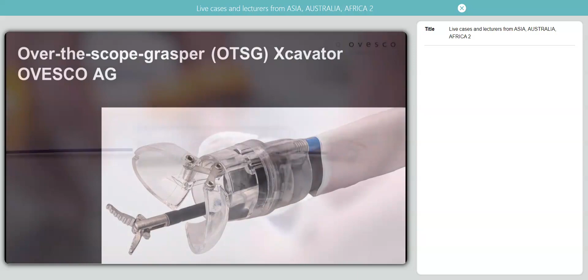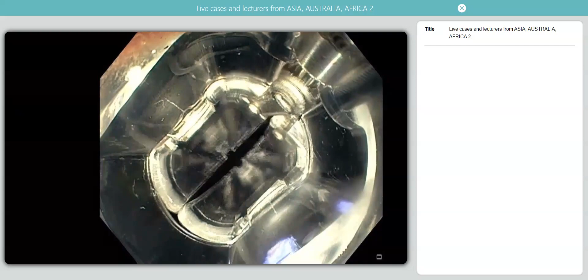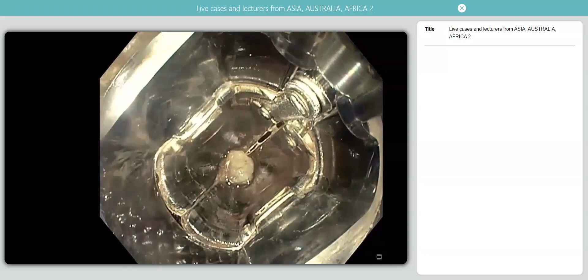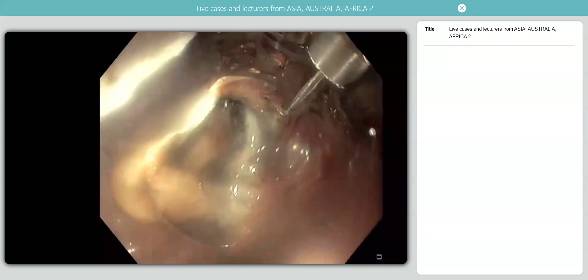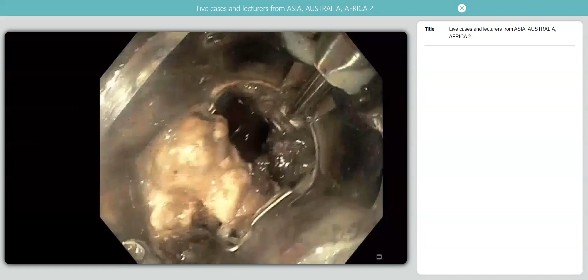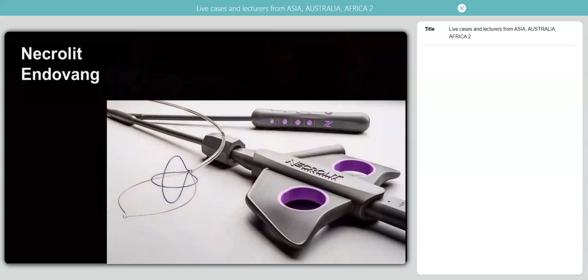The second device for endoscopic necrosectomy is the over-the-scope grasper Xcavator by Ovesco. It is a grasper mounted over the scope with a scoop span of about 28 mm. It is suitable for gastroscopes with an outer diameter between 9.5 and 10.5 mm. Once mounted, it adds about 4 to 5 mm to the outer endoscope diameter, and its passage is possible only through LAMS with a diameter of at least 15 mm. The device is mounted outside the patient over the tip of the gastroscope and then secured to it. The necrotic material inside the collection is aspirated or grasped inside the scoop. Then the scoop is retracted into the gastric cavity, where the necrotic material is released by opening and closing the scoop and with the help of the dedicated forceps.